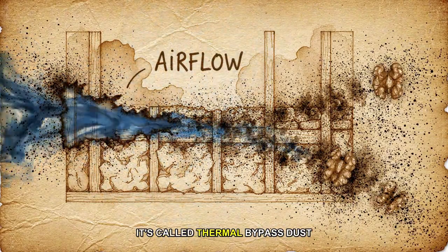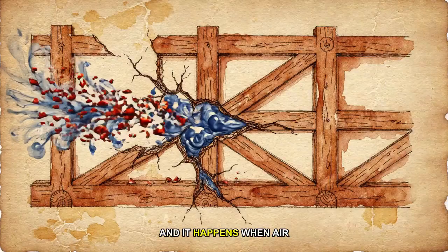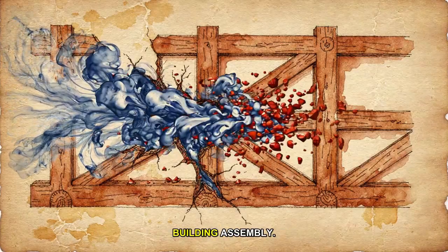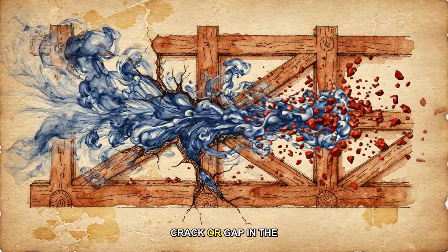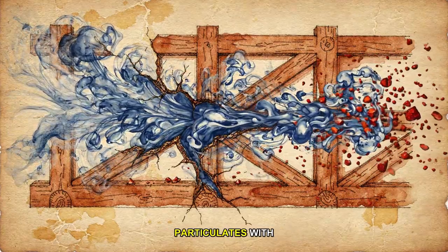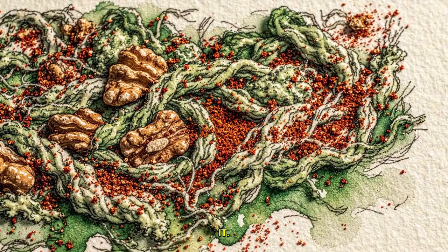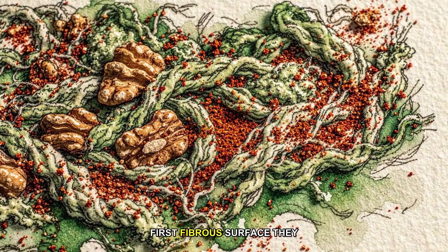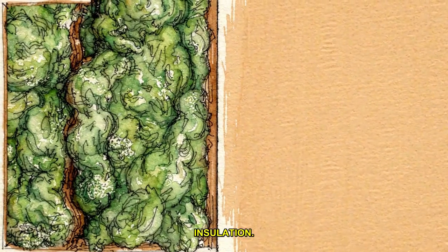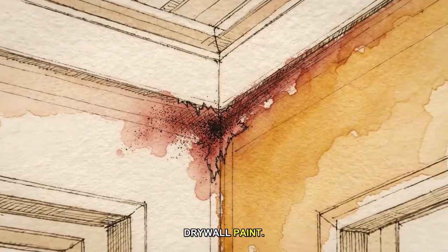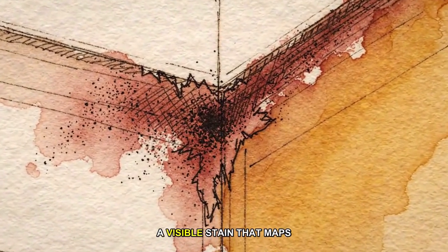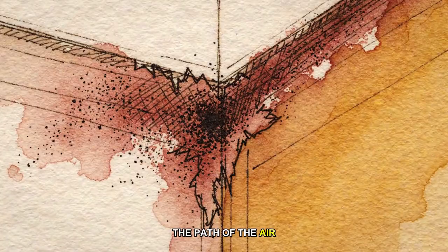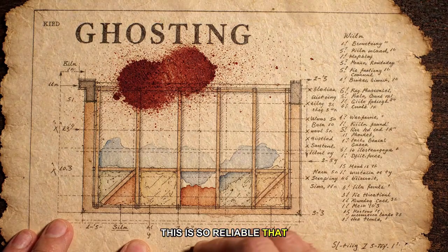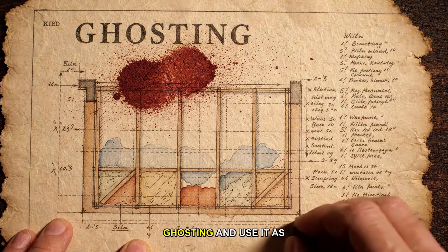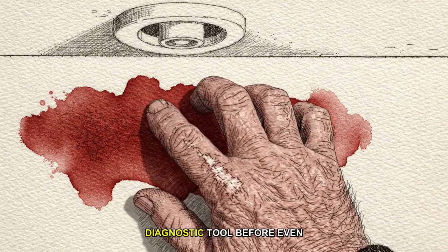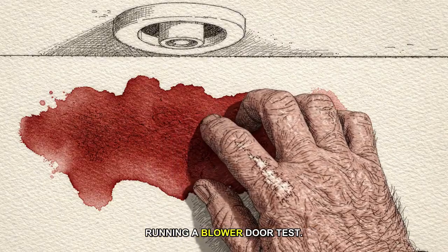It's called thermal bypass dust marking, and it happens when air moves through gaps in the building assembly. As air travels through a crack or gap in the structure, it carries fine particulates with it. Those particles deposit on the first fibrous surface they contact: insulation, drywall, paint. And over time, they create a visible stain that maps the path of the air leak exactly. This is so reliable that building scientists call it ghosting and use it as a low-tech diagnostic tool before even running a blower door test.